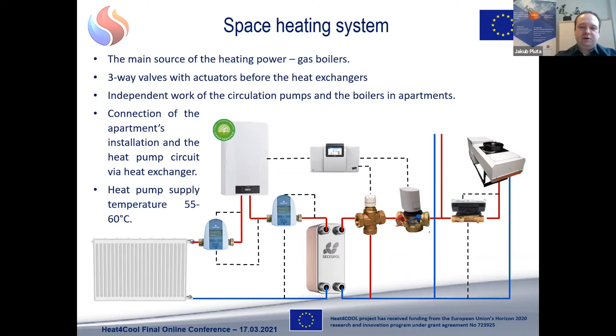Also, to prevent the situation where the water in the first circuit is heated by the installation of the apartment, we installed next to each heat exchanger a three-way valve controlled by the controller, which runs the water in bypass if the temperature supplied by the heat pump is lower than in the internal installation of the apartment. The heat pump is able to provide to the apartment a supply temperature between 55 to 60 degrees. It has a possibility to provide higher temperatures, but according to simulations before the retrofitting, these temperatures allow us to achieve the biggest efficiency of the system.